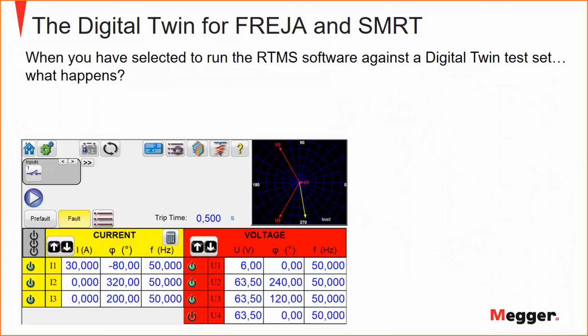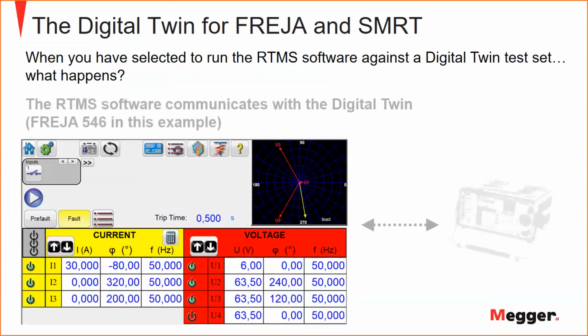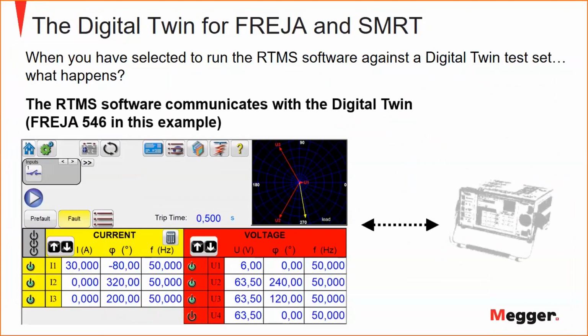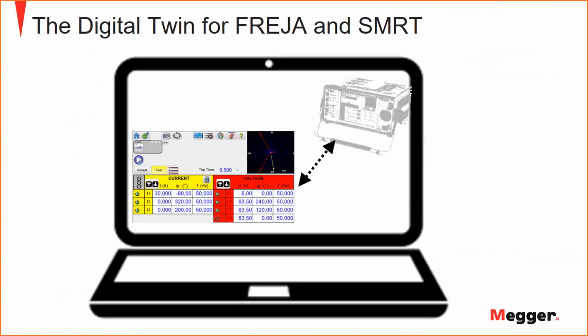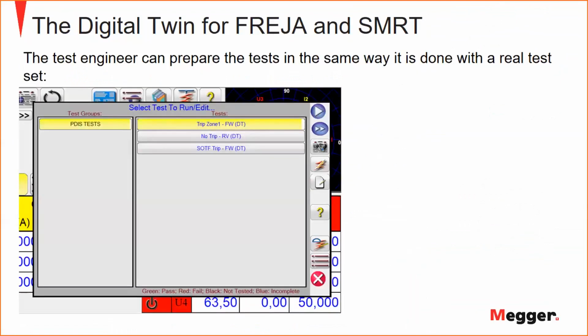So what happens when you select to run RTMS software against a digital twin test set? Well, the RTMS software normally communicates to the real test set through an Ethernet port, Ethernet traffic, cable at the end, or USB, but a physical cable. Now there is a physical cable, but it's not there. It's in the computer because the test set is running in the computer. So the communication is there, but it runs in your computer. So you don't see it, but it's done. RTMS doesn't even understand that it's a digital twin.